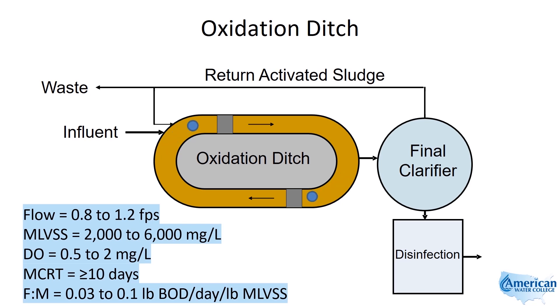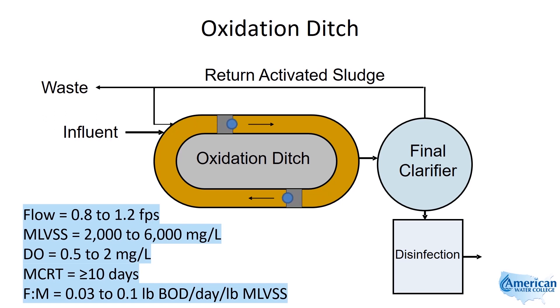The normal mixed liquor volatile suspended solids concentration in an oxidation ditch is in the range of 2,000 to 6,000 milligrams per liter. If the ditch develops a crisp white foam, the operator should reduce sludge wasting, as this indicates a young sludge or low MCRT. If a dark foam forms, the operator should increase sludge wasting, since this indicates old sludge or a high MCRT.